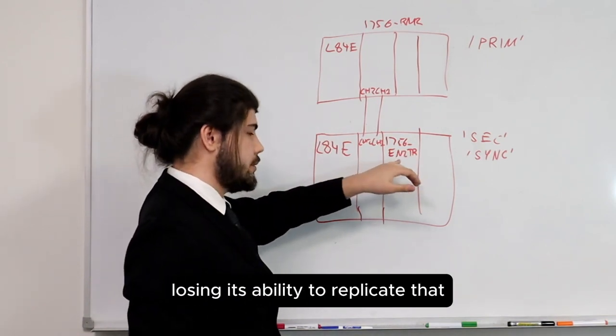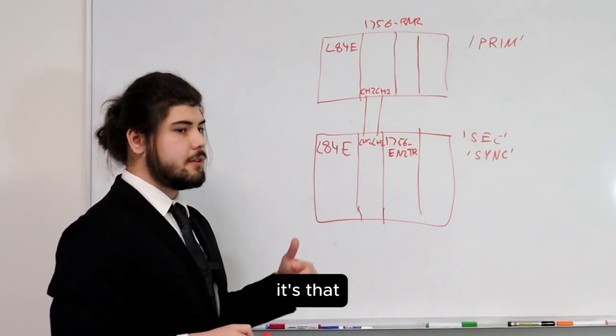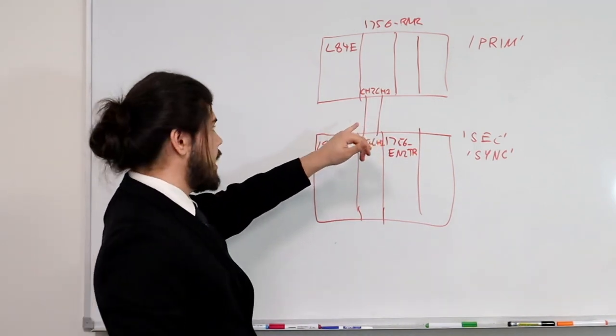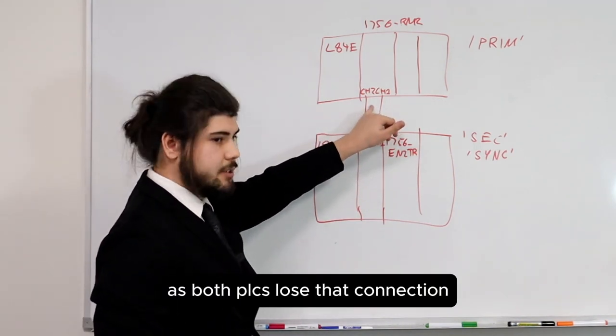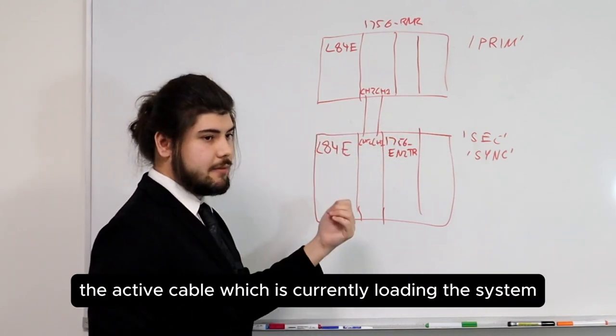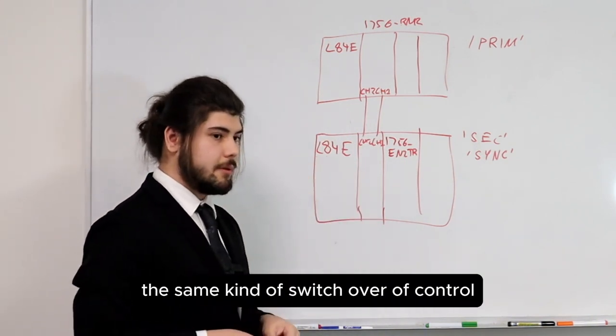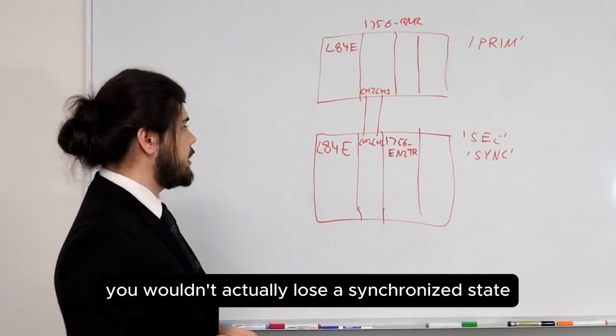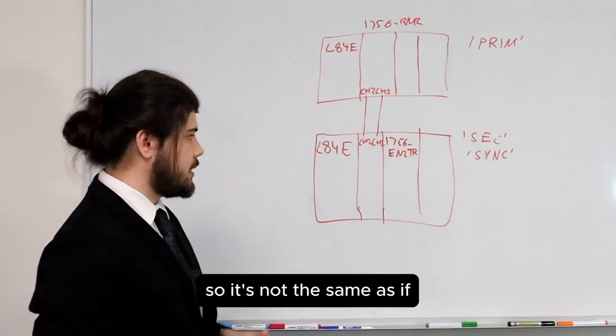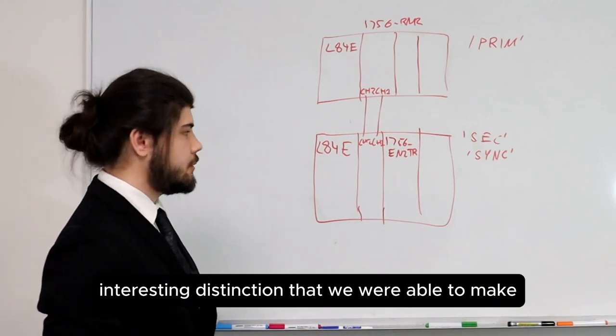As a result of losing its ability to replicate, it would become disqualified. It's not necessarily that they've got to communicate to each other — it's that they've got to communicate to the same field device. If I were to unplug a cable and both PLCs lose that connection, it won't perform a switchover event. A switchover event only occurs if I unplug the active fiber optic cable currently loading the system — it would switch over to the redundant cable. You wouldn't actually lose synchronized state because the system can still perform its cross-loading operations properly. So it's an interesting distinction between losing an external communication connection versus losing the fiber optic cross-load link.